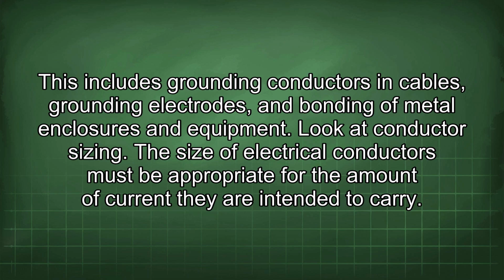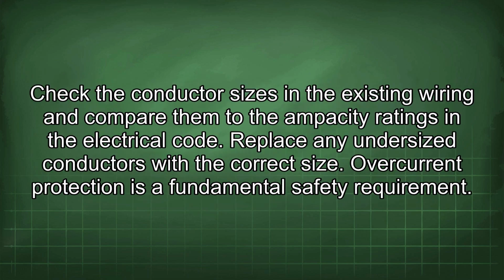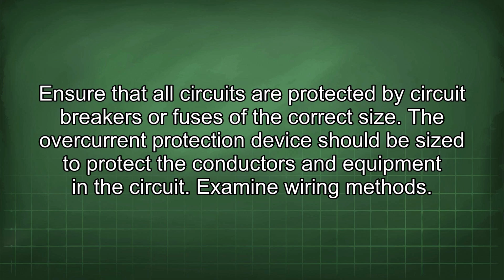Look at conductor sizing. The size of electrical conductors must be appropriate for the amount of current they are intended to carry. Check the conductor sizes in the existing wiring and compare them to the ampacity ratings in the electrical code. Replace any undersized conductors with the correct size. Overcurrent protection is a fundamental safety requirement. Ensure that all circuits are protected by circuit breakers or fuses of the correct size. The overcurrent protection device should be sized to protect the conductors and equipment in the circuit.